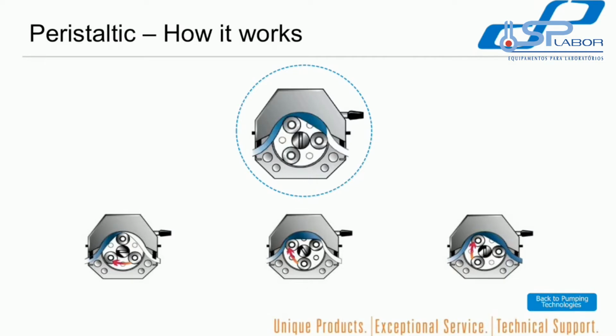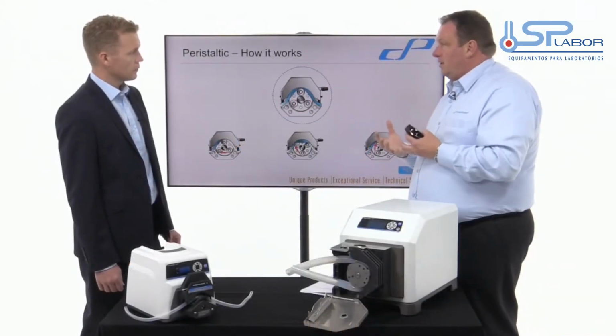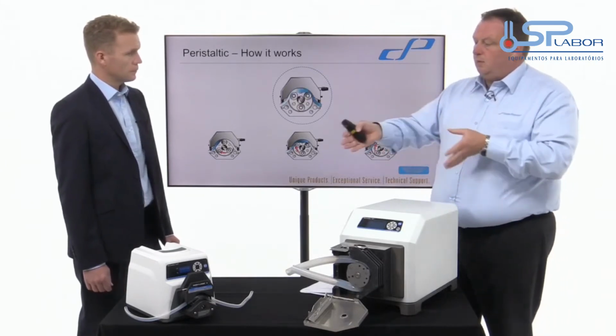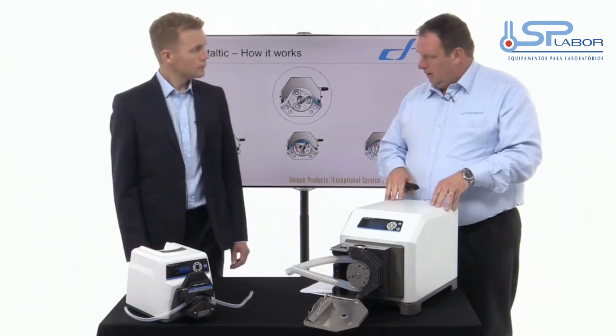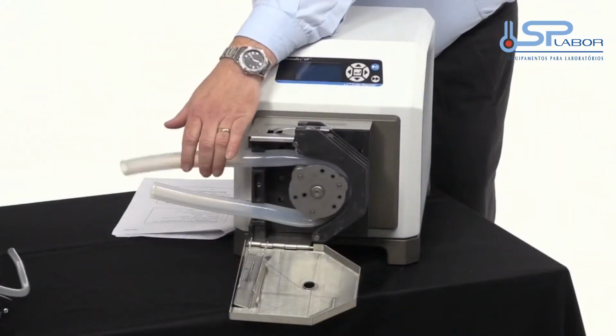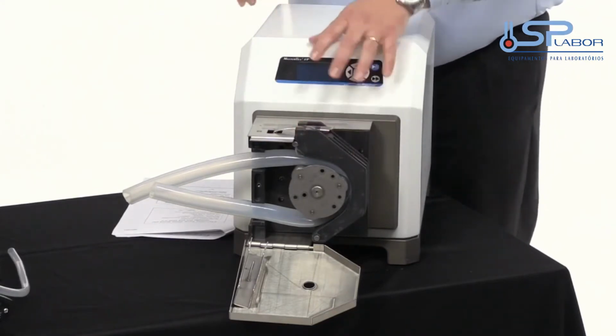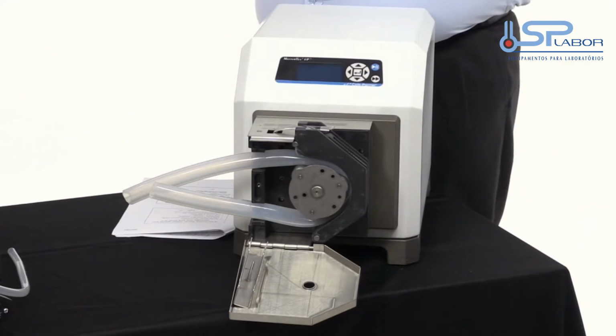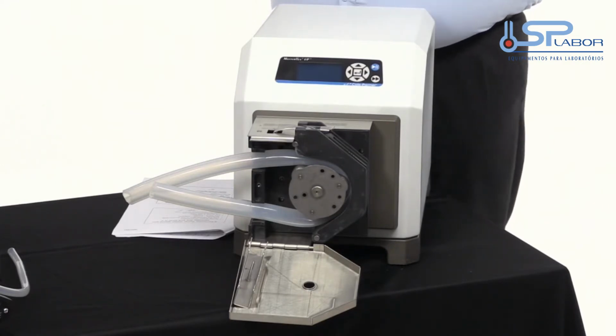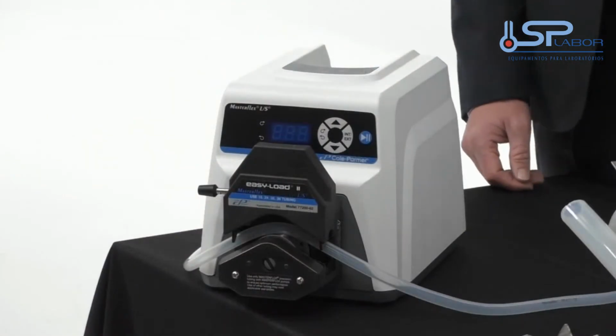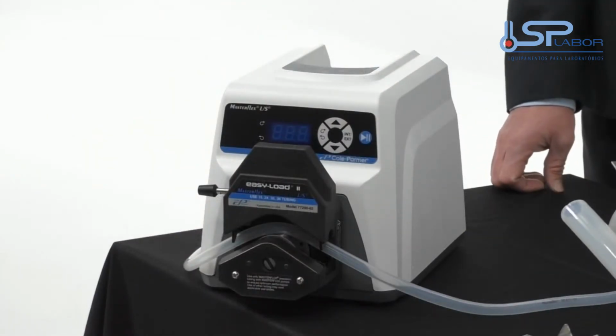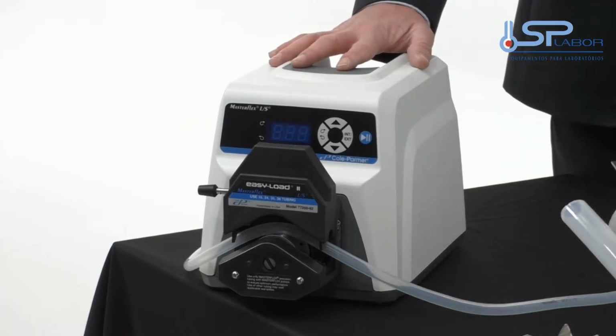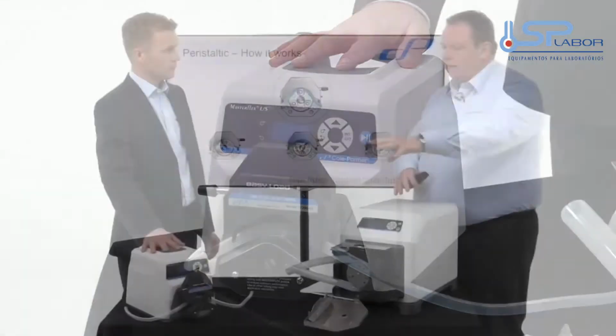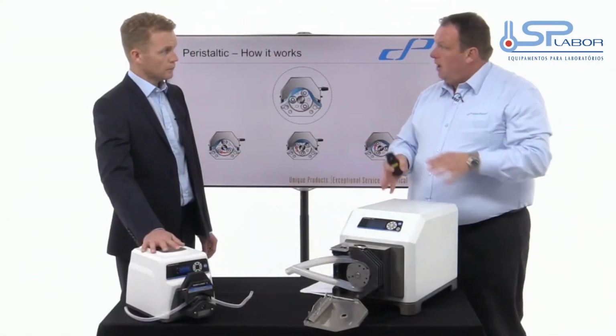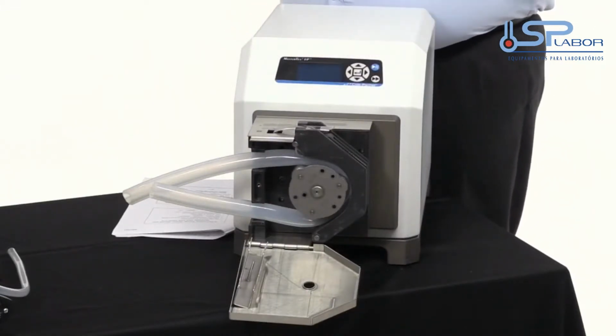The pump is the tube. The pump head is how we squeeze that tube and move the liquid along it. And then the rest is the control. If we look at the table, we have 2 different sizes of pump on here. But the pump is the tube at the front. We then have the pump head that squeezes the tube, and we have the control system, from basic controls, which is just a variable speed control, which I think is what we've got on that smaller one, to process drives, which are computer compatible. We have the same with the smaller units. They're a laboratory scale or a finer scale. We do modular ones, which means you have the pump and motor. These units contain a motor separate to the control, but they are a very, very variable control.